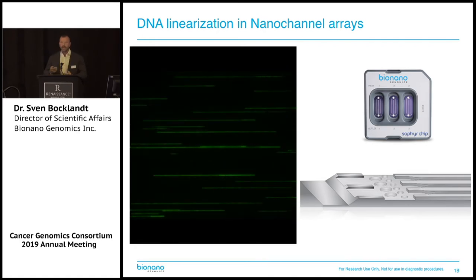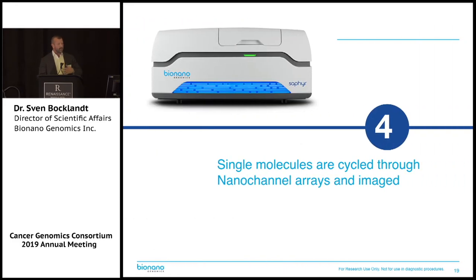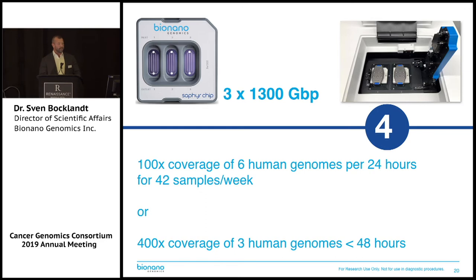We don't collect data while the molecules move — we do that when they're paused. The instrument cycles molecules in the channels, images them, and cycles new ones in over and over again. That gives us the capability to run six human genomes per 24 hours at 100x coverage for diploid genomes, or collect as much as 400x — 1,300 gigabase pairs of data — on each of the three flow cells on a chip in less than 48 hours. We'll be increasing this throughput later this year with a software update.